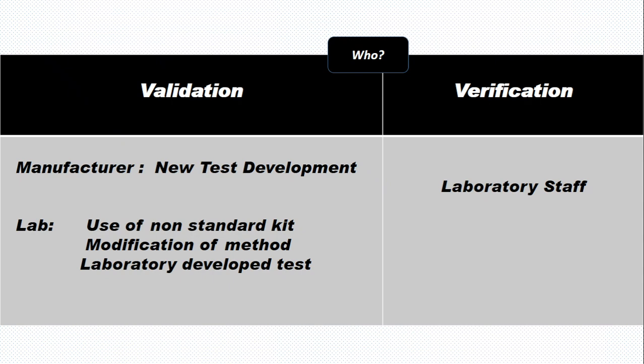This means when a manufacturer develops a new machine or test method, they need validation before selling it to the market. On the other hand, the clinical lab needs validation when they use a non-standard kit. Let's say a kit that is not approved by FDA or CE. At this stage, they need to validate the kit before using it.